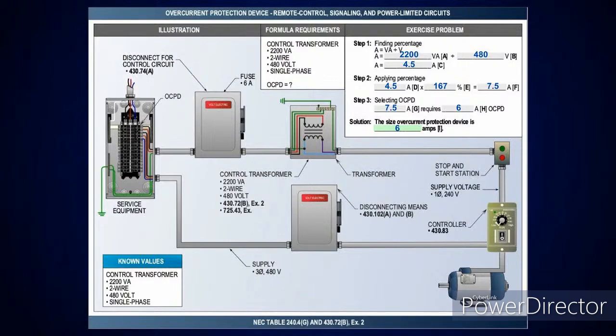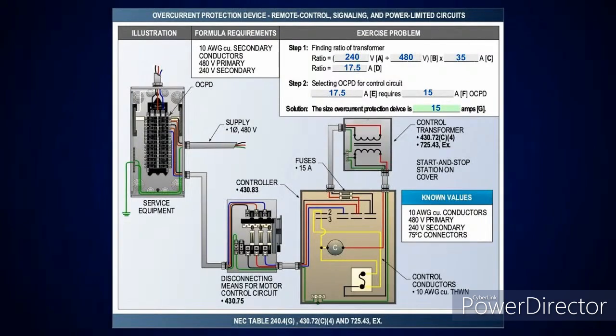Gotcha. Okay. All right. Now, here's another one. I've got another control transformer here, and I'm going to be looking at sizing this overcurrent protection device. As I look at this, you're going to need to go over and look at table 310.16, and I'll show you why here. I'm going to prove a point here.